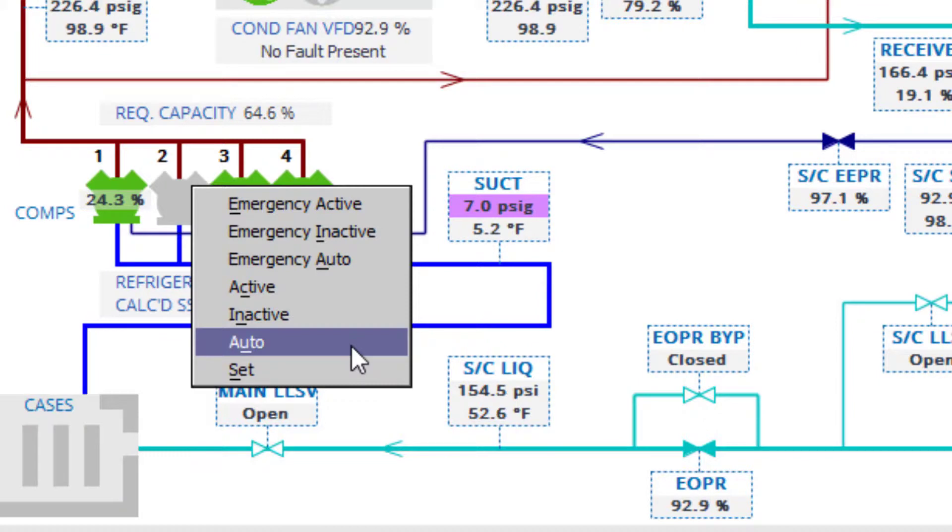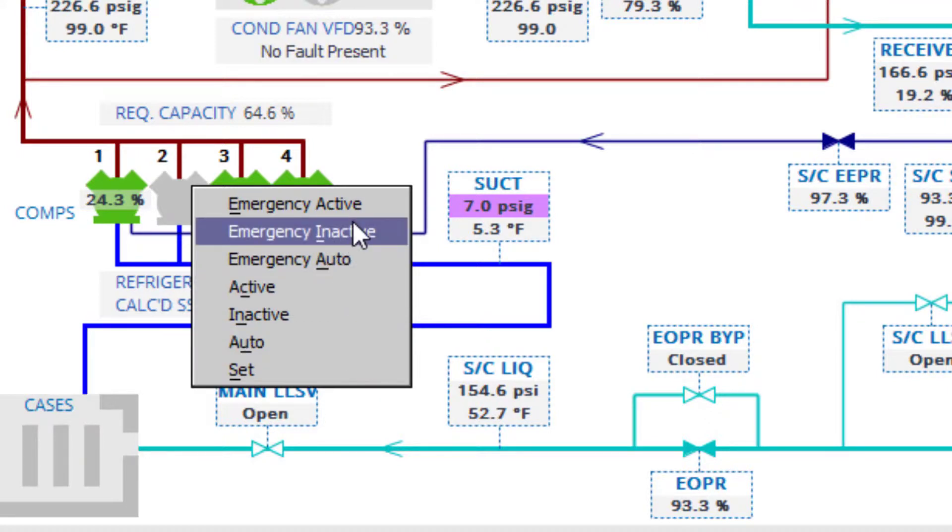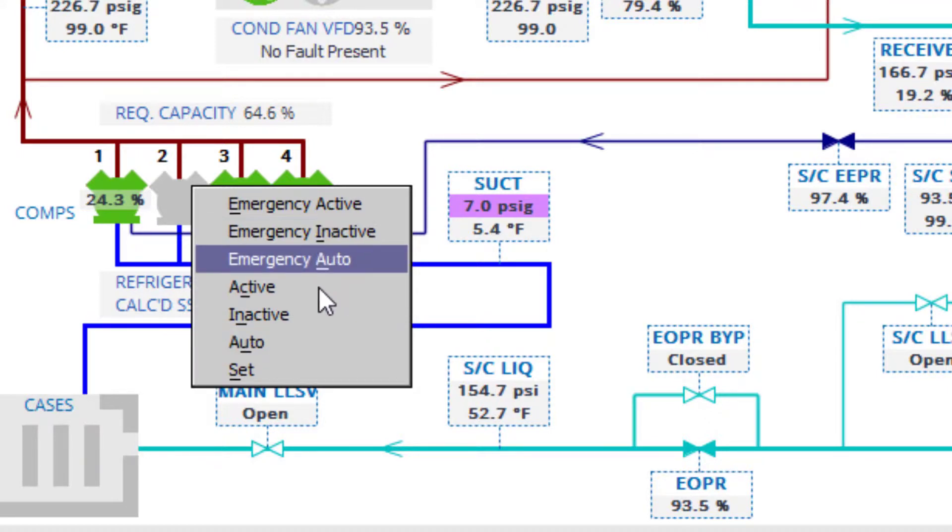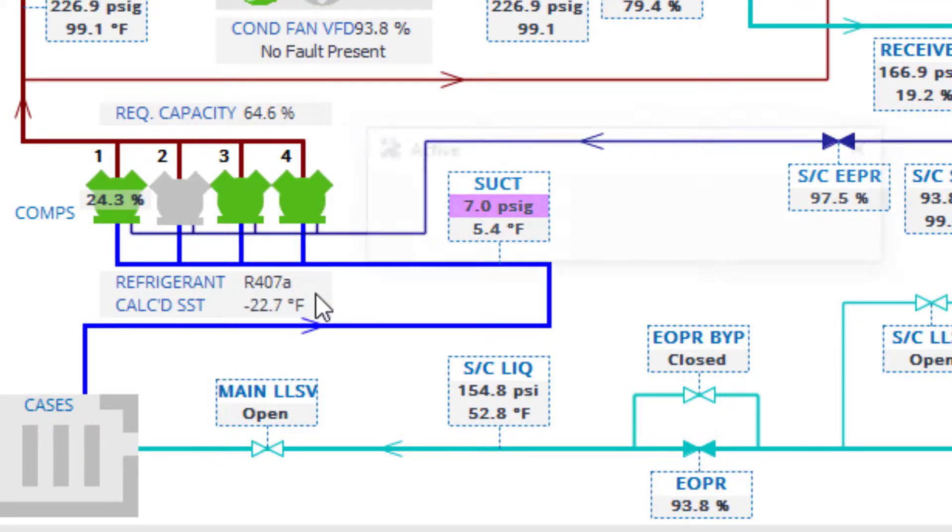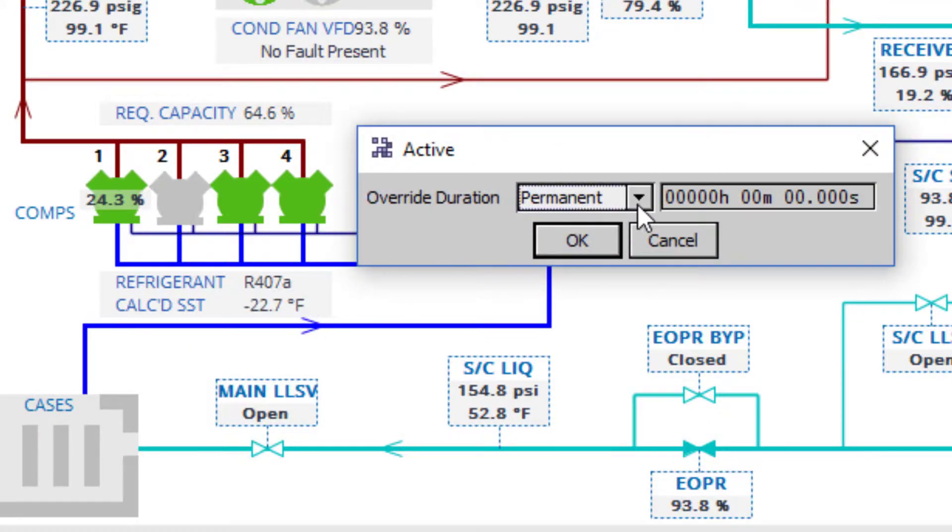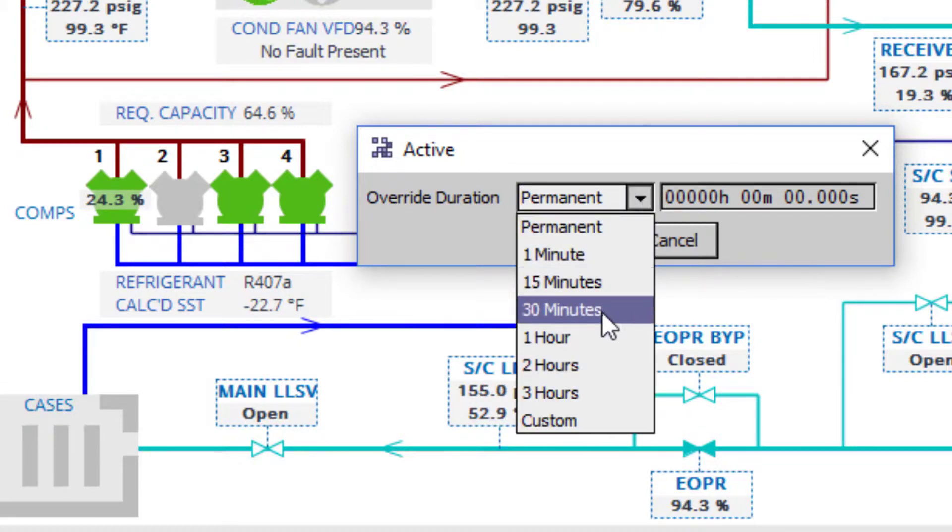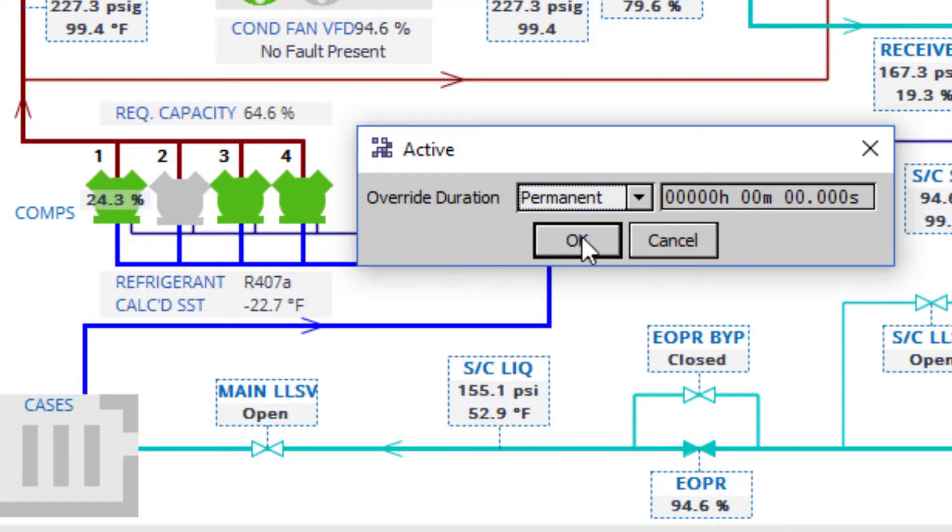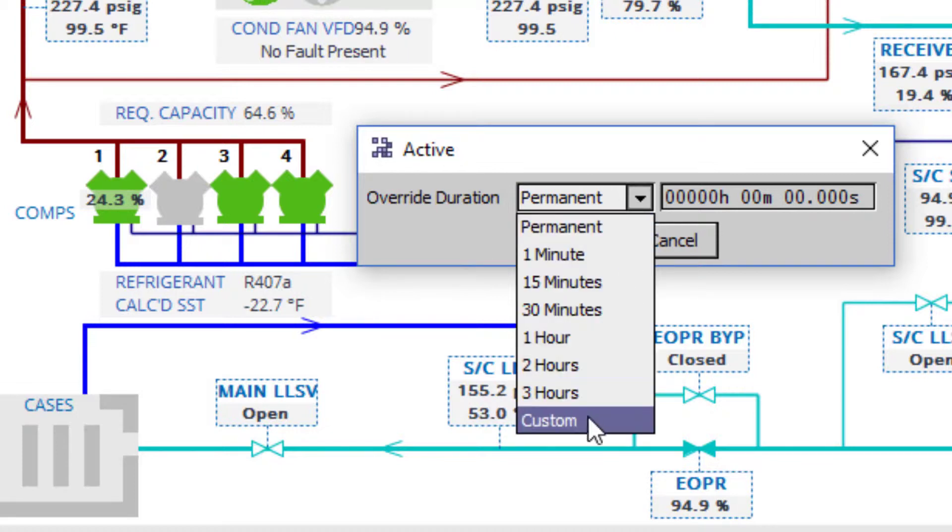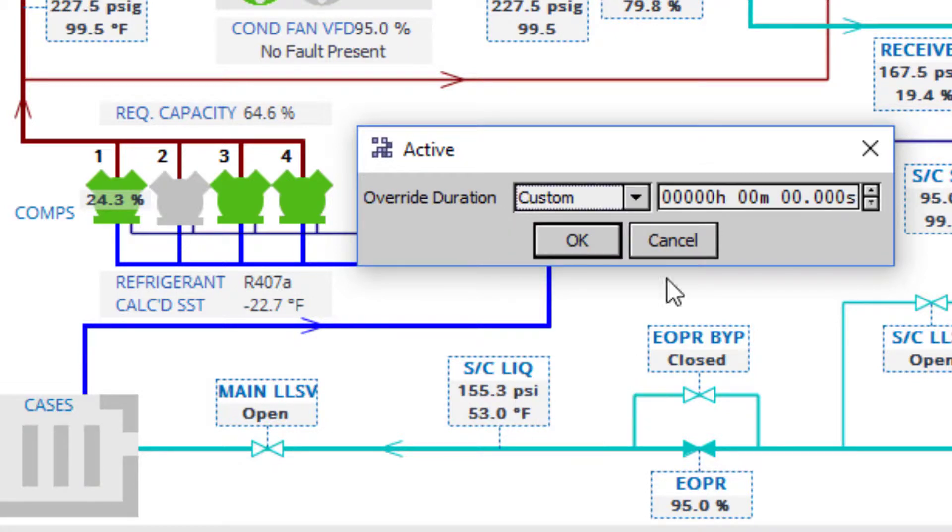A good practice while forcing overrides is to always use a timed duration. The permanent duration will keep a point forced until manually set back to auto. In most circumstances, it is preferred and safer to use a timed duration in the event that a critical point has been forgotten and left in an overridden position.